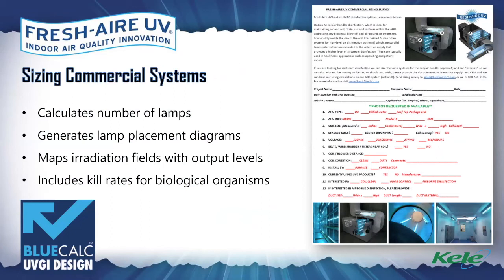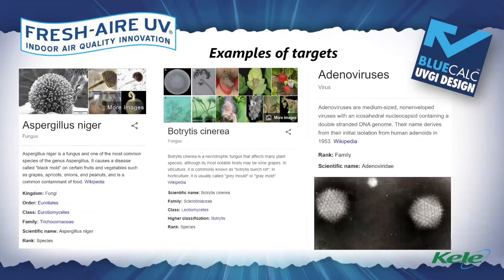We have a very robust Blue Calc sizing program, industry leading. And we have a survey, and we ask you to fill it out if you want us to tailor our sizing calculations to your specific application. What we typically ask is the width and height of the coil and CFM, as well as the duct dimensions, width and height of the duct, for our airstream disinfection. We will take those numbers and base it on any number of biological targets. I like using Aspergillus niger for coil disinfection.